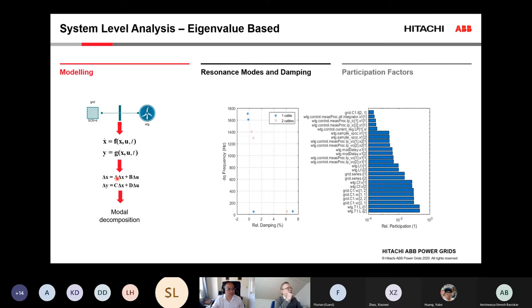The result of this modal analysis comes out in the form you see here in the middle, where we detect a number of resonance modes. Each resonance mode will have a certain damping and a certain frequency. The crosses are the resonance modes with two cables in operation, and the stars relate to when we have one cable in operation. With one cable in operation, we can see that two of the resonance modes have a negative damping, and negative damping means unstable. How this modal decomposition works will be the topic of the second talk.